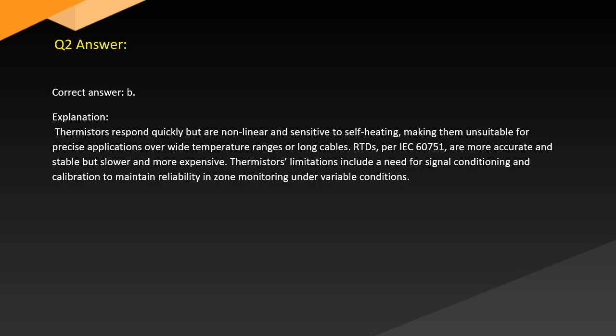Answer. Correct answer B. Explanation. Thermistors respond quickly but are nonlinear and sensitive to self-heating, making them unsuitable for precise applications over wide temperature ranges or long cable runs. RTDs per IEC 60751 are more accurate and stable but slower and more expensive. Thermistors' limitations include the need for signal conditioning and calibration to maintain reliability in zone monitoring under varying conditions.